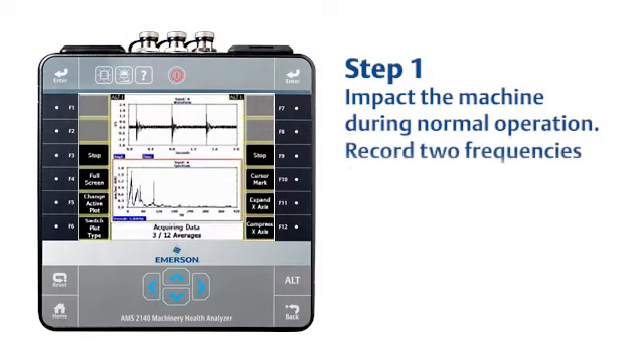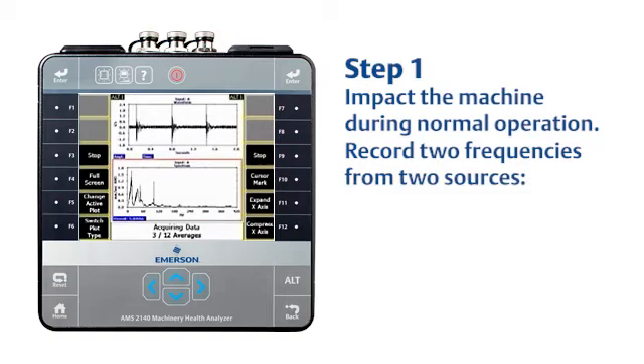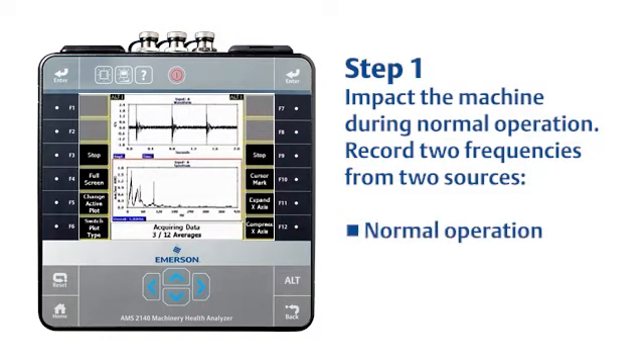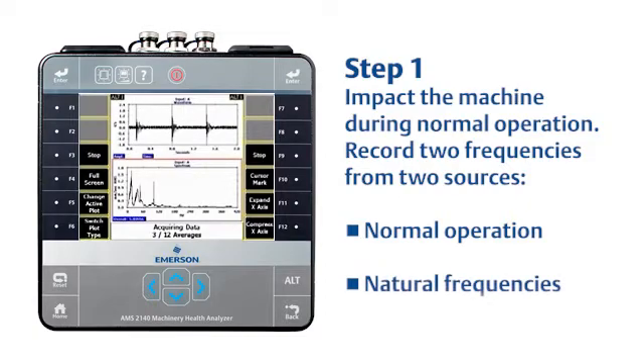Negative averaging is a two-step process. First, while the machine is running, you impact or strike the machine repeatedly to create and measure two frequencies. One will be the normal operating frequency, including things like imbalance, misalignment, looseness, and more. The second measurement will be the natural frequencies caused by the impact.